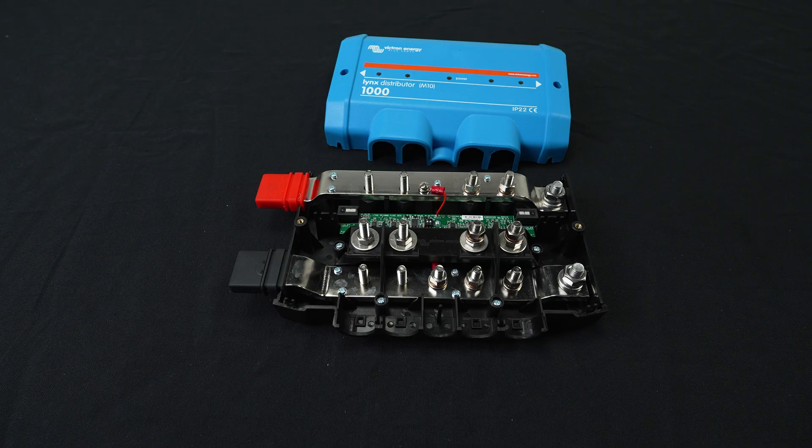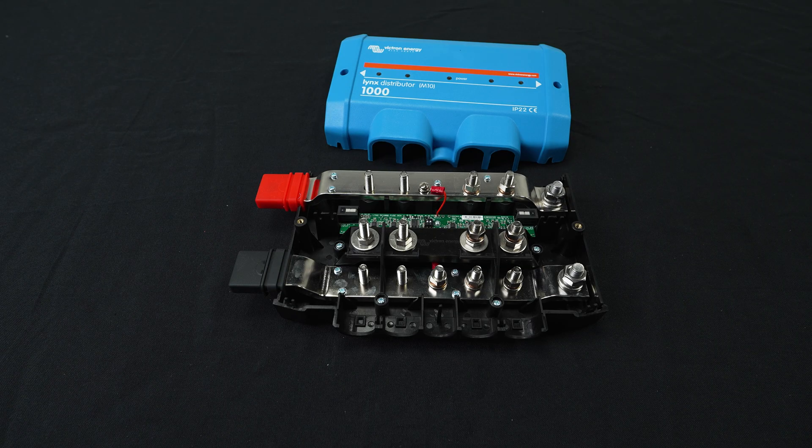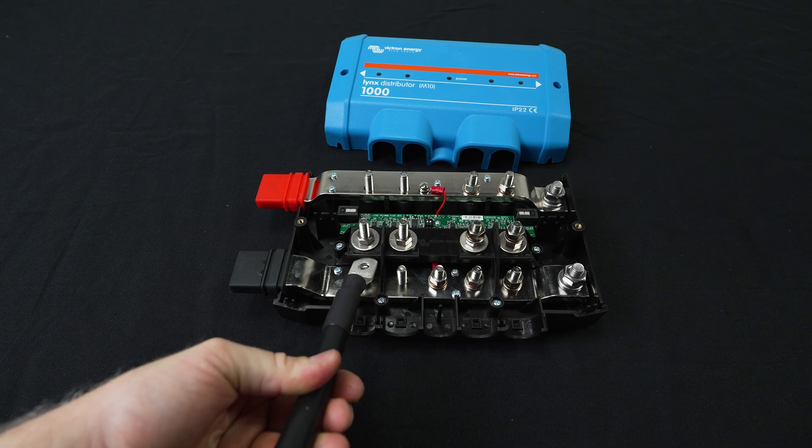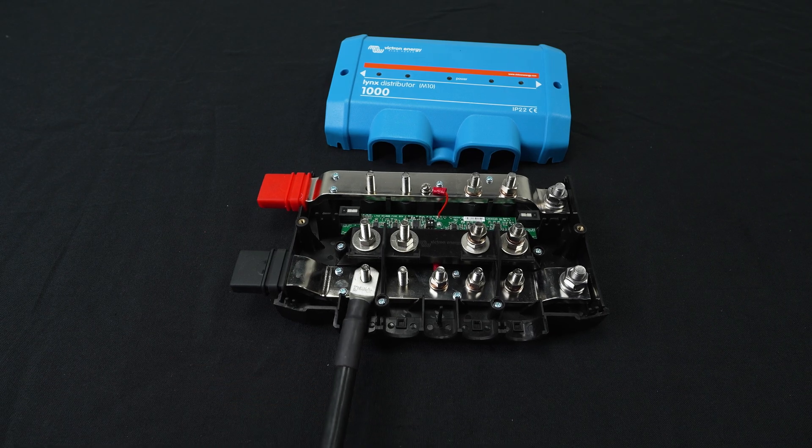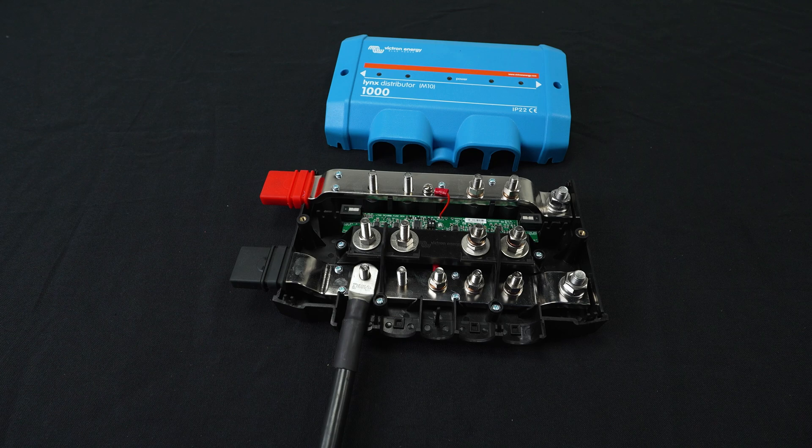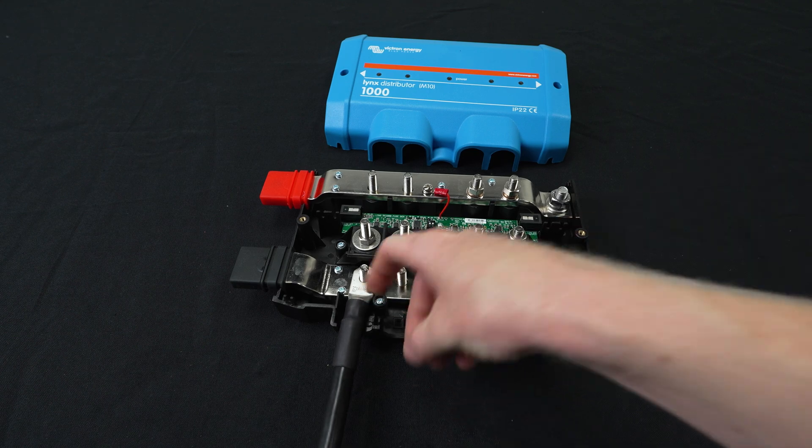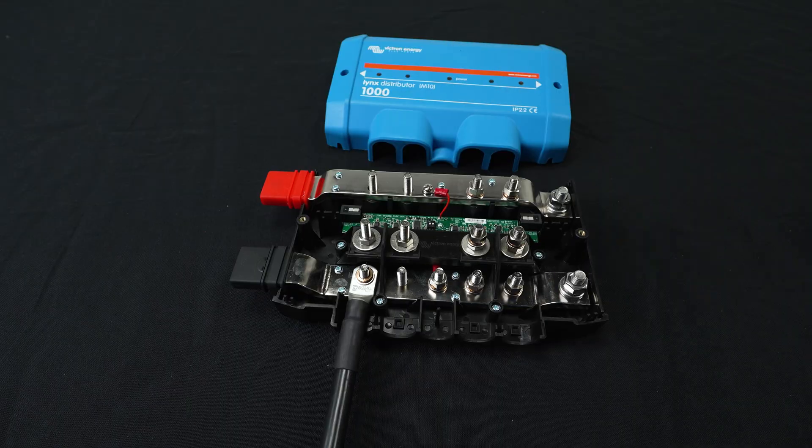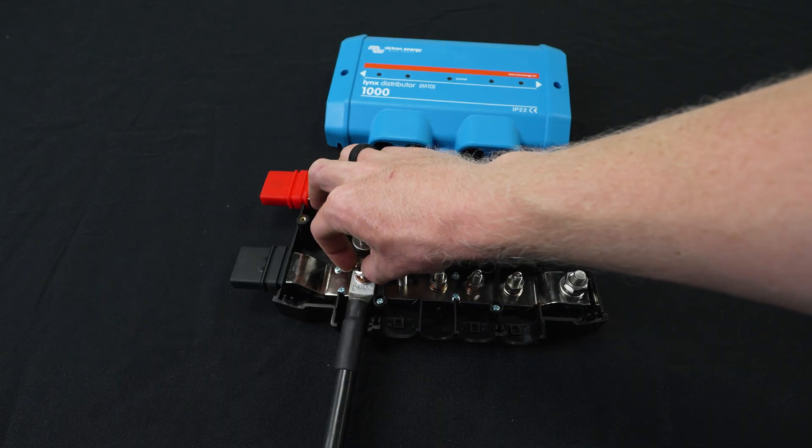So we'll attach our negative cable first. Today for our example we're going to use a 2 AWG cable with a 5/16 lug. And we're going to put our lug down first, then our flat washer, then our lock washer, and finally our nut.